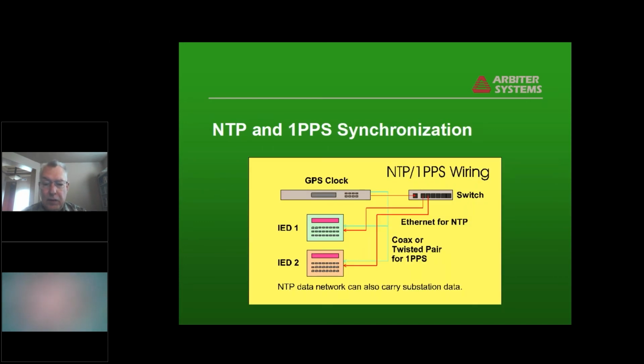This is kind of how you'd go about distributing time if you wanted to use NTP and 1 PPS to provide finer resolution. The NTP signal goes over the red lines through the network switch to the IEDs, and the 1 PPS is transmitted, typically over a coaxial transmission line, to the IEDs directly.